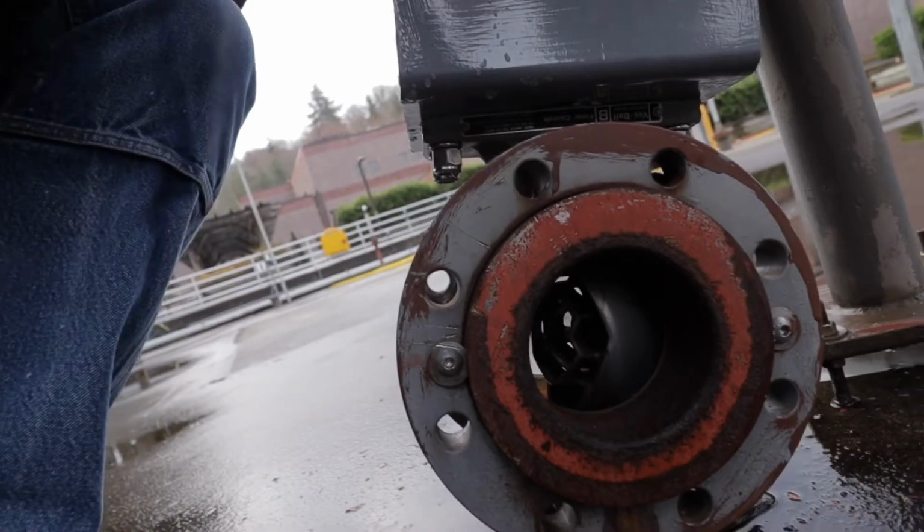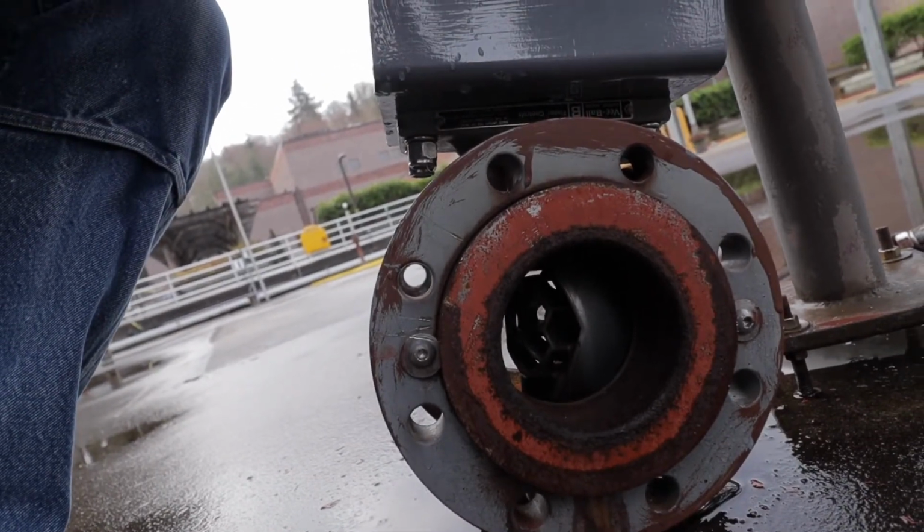Well, the indicated position on the actuator doesn't line up with the position of the flow control valve. I've set the actuator to full open, and you can see the V-ball's not open all the way. Just that 20 or 30 degree difference can totally account for the loss in flow. So an actuator that's slipped out of position is not really a common thing, but it does happen. It's important to remember to identify these things early on. It's easy to look at, it only takes a minute to verify.